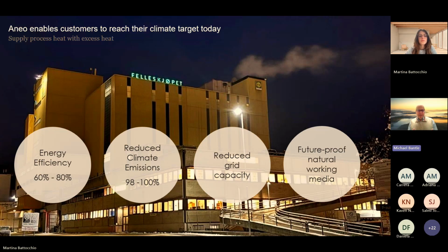So most clients simply, the first approach is, okay, we are getting rid of the gas or oil boiler and putting in an electric boiler, 10 megawatt, 20 megawatts. In the first phase of this project, quite often they realize that there's not enough capacity available, and in the future there will be even less chance of getting a 20 megawatt cable for a 20 megawatt boiler. So if you want to electrify, but you don't get enough electricity to direct electrify, you end up at a certain point talking about heat pumps.